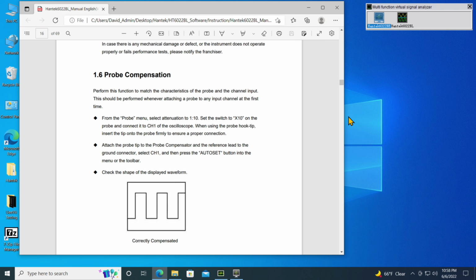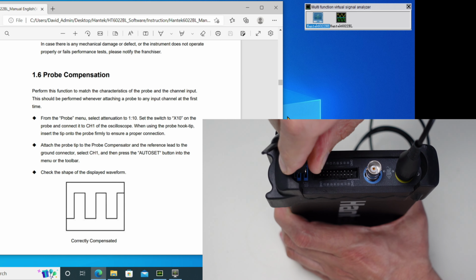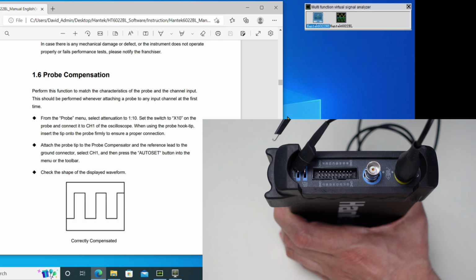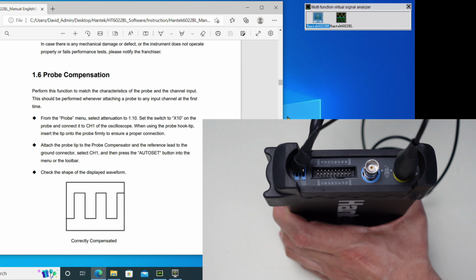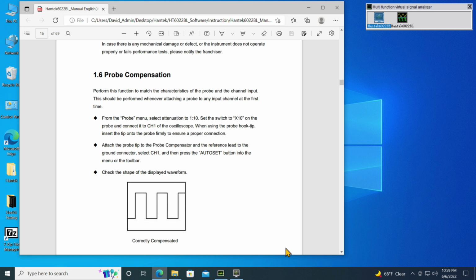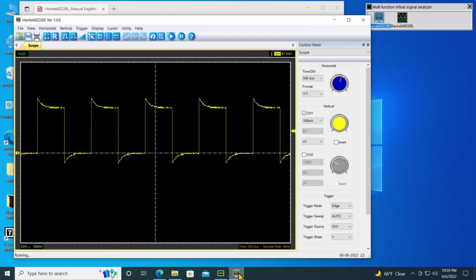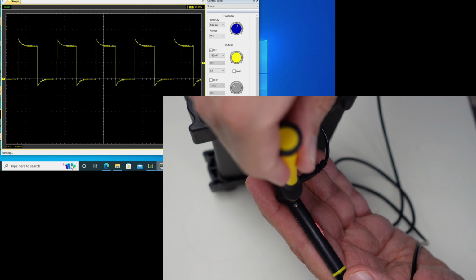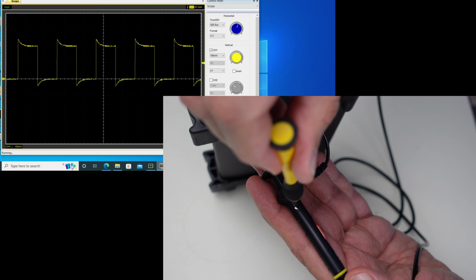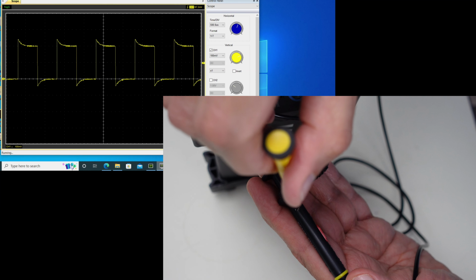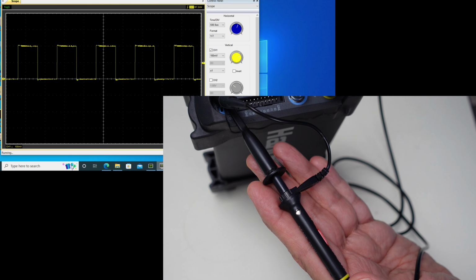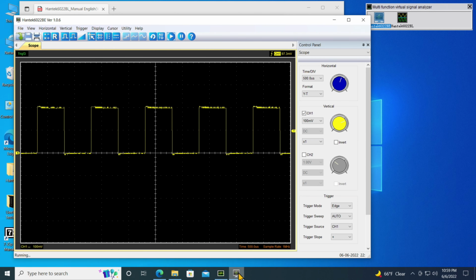Now in the instructions, they tell you how to adjust the probes, basically compensating for any stray magnetism or inductance or capacitance. If you follow these instructions here, you will then see this. And as you can see, if you look at the instructions, that means that I am not properly compensated. So I will take a non-magnetic screwdriver, put it into the little adjuster at the top of the probe, in the center of the probe actually, and I will tweak that until it comes down to as square as possible. Do each probe independently. So this is the yellow one. Do the second one as well for the green one when it's connected up into its appropriate BNC connector. And then we're all set to go.